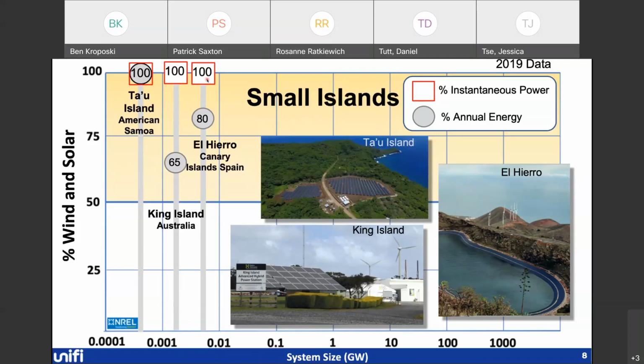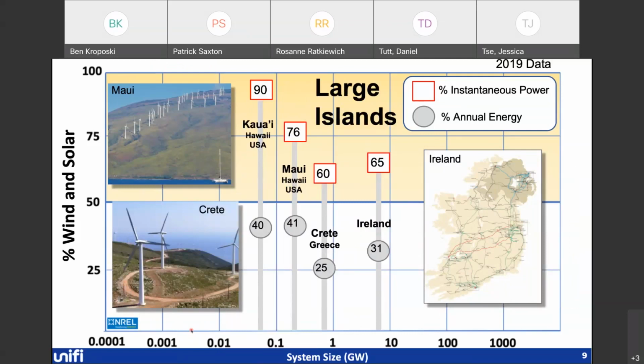Now, the key thing here is that these are all very centrally controlled. We have one place where all the inverters are co-located together. They are not distributed around the island at all, and we can set up all the protection for these systems in a very small location. But we know how to do it. If we go to slightly larger systems, now we start to move into systems that look much more like the grid that you would know. So we start off in Hawaii with Kauai and Maui. These systems have generation distributed all over the island. They have some large plants. This is a large wind plant on Maui, but they also have distributed photovoltaics on people's roofs.